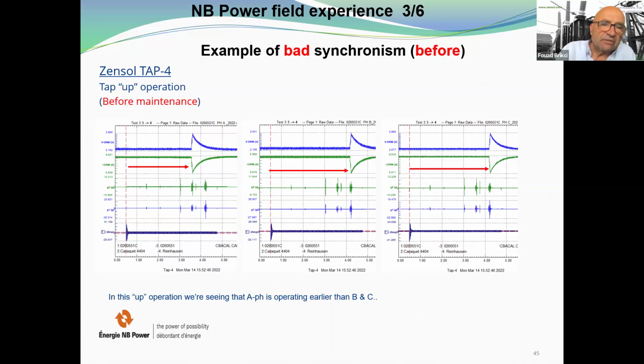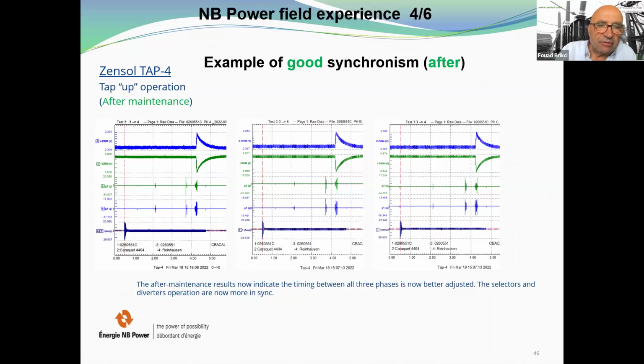So in fact, you can see that this impact is related to this diverter thanks to the DRM, and thanks to the current, we are able to detect the switching operation time and compare it to phase B and C. And after maintenance, the results now indicate the timing between all three phases is better adjusted. And the selectors and diverter operation are now more in synchronization. So here you see, and they operate exactly at the same time.